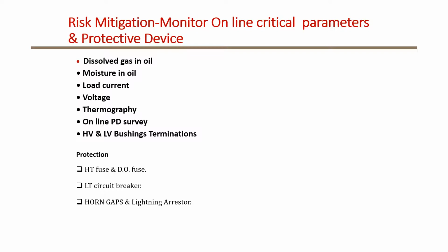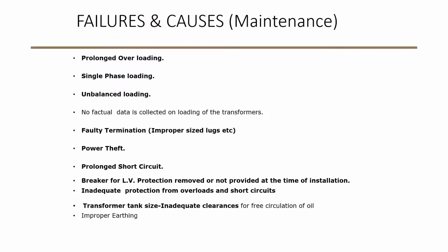These are all components for mitigating risk in distribution transformers. Still, problems exist, like prolonged overloading—meaning we don't monitor voltage and current, keep overloading the transformer, and then blame the failure on overloading. Single phase loading is also dangerous for a three-phase transformer, and unbalanced loading is not good because it creates harmonics, which cause additional heating issues in the transformer.